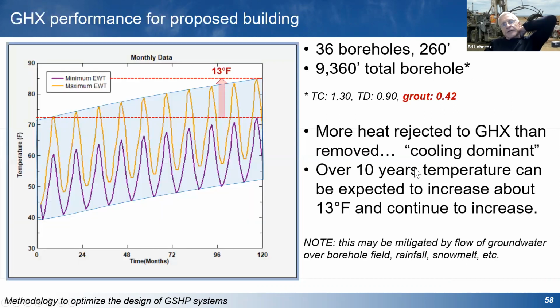Looking at the long-term performance, here we've looked at standard grout over a 10-year period, and we're looking at about a 13-degree temperature increase. And that's assuming that there's no mitigating impact from water flow across the borehole field or infiltration of water through sand and gravel geological conditions. The building is obviously cooling dominant, so in some situations you may get this kind of increase. In other situations, it might not be this drastic. But until you start running the system for a while and really know the impact of groundwater flow and things like that, it's difficult to model.